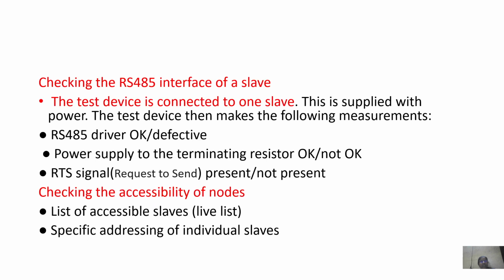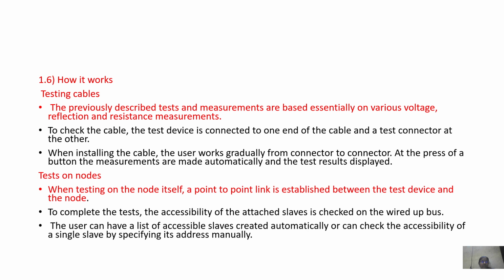So the test device is connected to one slave, which is supplied with power. The test device then makes the following measurements: whether the RS485 driver is okay or defective, whether the power supply to the terminating resistor is okay or not okay, and whether request to send is present or not present. Also it checks the list of accessible slaves and addressing of individual slaves.